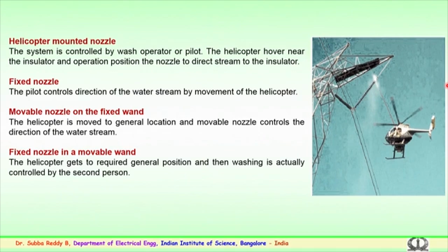So, this is carefully adjusted. You require a lot of skill when you are near the high voltage transmission lines, and the pilot and also the trained personnel who are using this water jet have to be properly trained to use the system. With fixed nozzles, sometimes the pilot controls the direction of the water stream by movement of the helicopter, depending upon the arrangement. The distance, as mentioned, again is a suitable minimum distance that has to be kept away from the transmission lines depending upon the voltage levels.